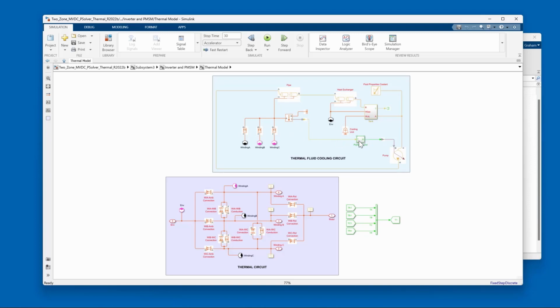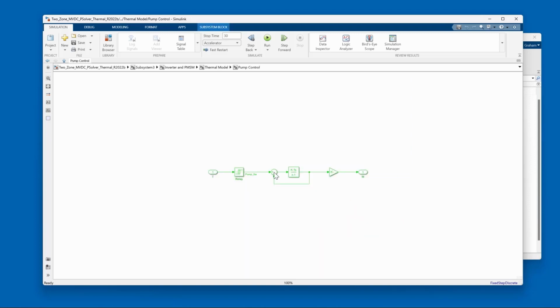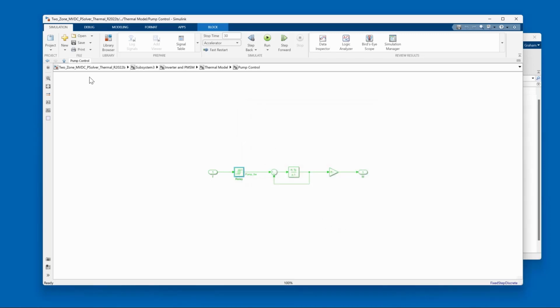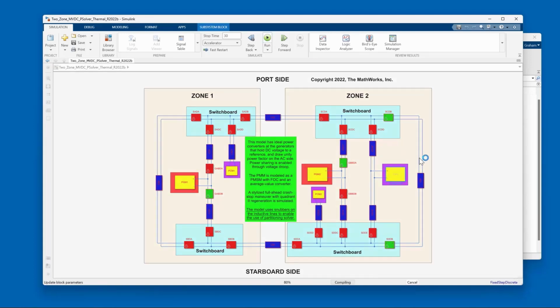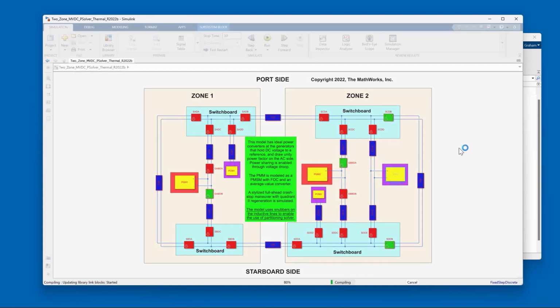The pump control is simple: if I go in here, I have a relay saying if temperature goes above 329 Celsius, turn the pump on, and if it goes below 320, turn the pump off. So a simple bang-bang type control here. I'm just going to simulate this, and while it's simulating, I'll make some more observations about this model.